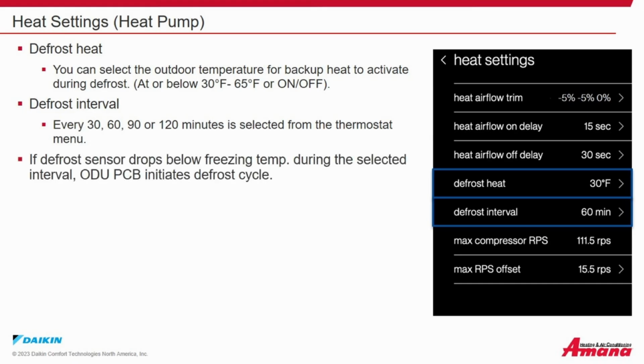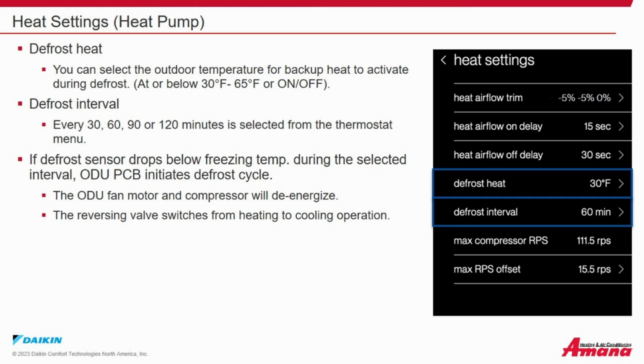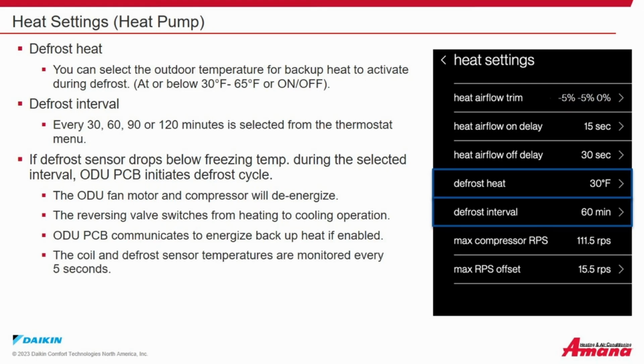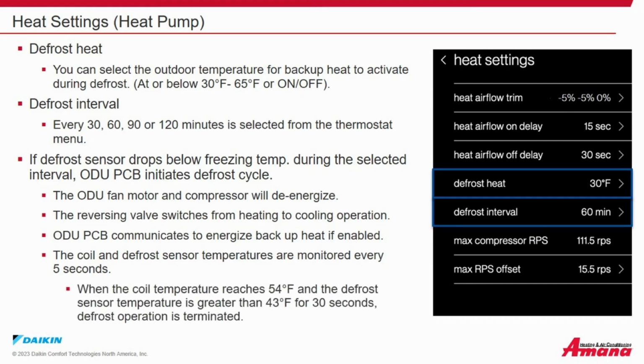If the defrost sensor drops below the freezing temp during the selected interval, the outdoor unit printed circuit board initiates a defrost cycle. The outdoor fan motor and compressor will de-energize. The reversing valve switches from heating to cooling operation. The outdoor circuit board communicates to energize backup heat if it's enabled. The coil and defrost sensor temperatures are monitored every 5 seconds. When the coil temperature reaches 54 degrees Fahrenheit and the defrost sensor temperature is greater than 43 degrees Fahrenheit for 30 seconds, the defrost operation is terminated.